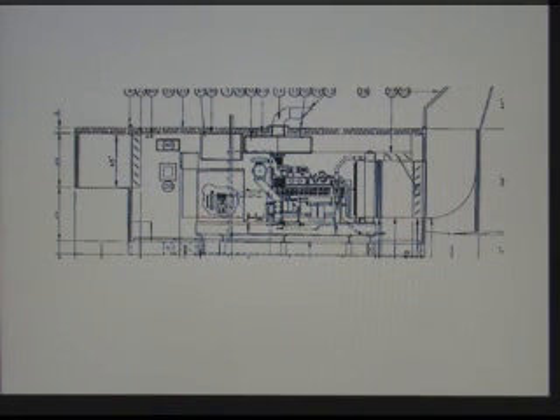One thing that's important to remember about the diesel engines is that they take fuel, they pump it up to a high pressure, and send it off to the injectors that are inside the cylinder heads, which actually injects it at the pressure required to overcome the compression of the cylinders. But they also use that fuel for lubrication of the injectors and for cooling of the injectors. So about 40 to 50% or more of that fuel gets heated up and is put back down into the day tank. So for installations that don't have a day tank, that excess fuel overflow has to go back to wherever that main tank is going to be, which could be some distance away, and then the small pump that's used for raising the pressure on the engine may not be suitable for that. That's why it's important to try to have a day tank somewhere nearby that the fuel can come from and then be returned to.